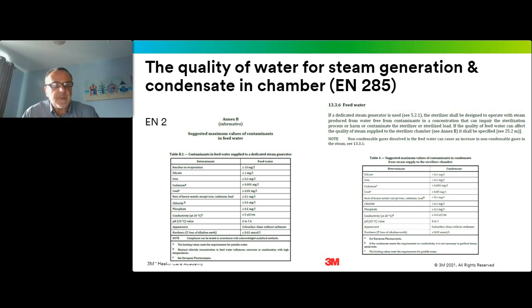So the expectation in many of the standards is that we use purified water in our feed water, and that the steam itself, when you condense it and analyze it, should not contain high levels of chemical contamination.